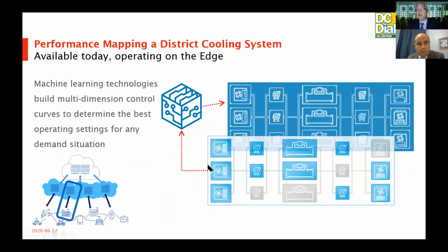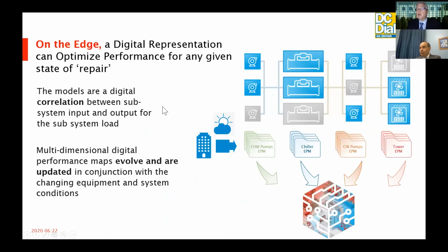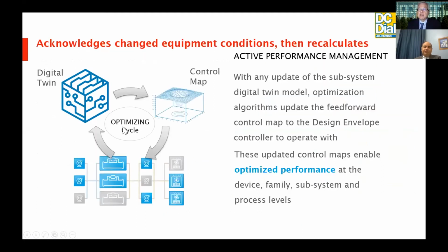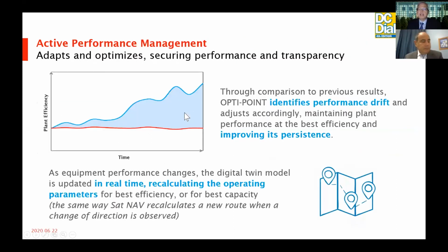And this is taken all the way up to the chiller plant level, where we calculate these digital twin models on the edge with today's higher speed and higher capacity processors, and enables us to create those advanced maps and give a correlation between the actual performance and what was expected to know what the state of repair is. And when that state of repair changes in a plant, maybe the cooling towers get fouled, we're able to recalculate with a new digital twin what the optimized control map is for that new condition of equipment. And also send out a message to the operator that we need to clean the fill on cooling tower number 3.